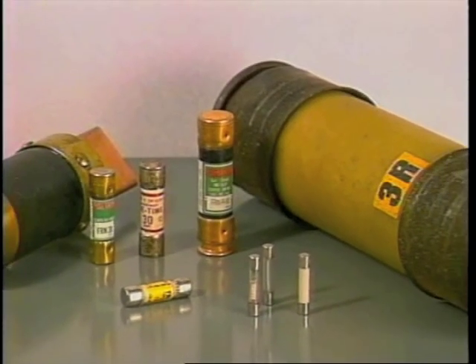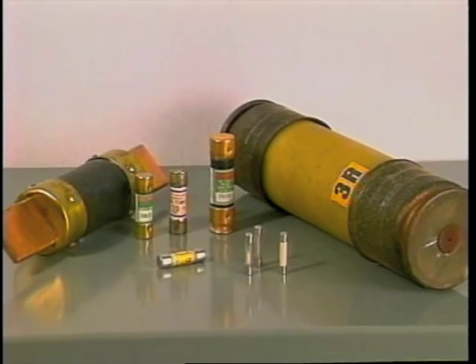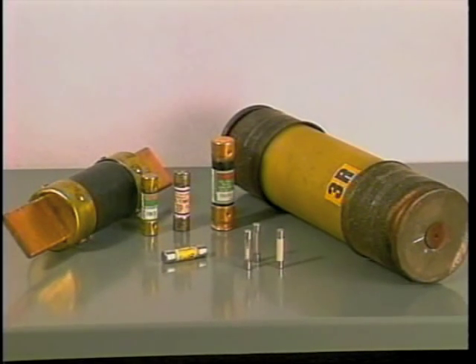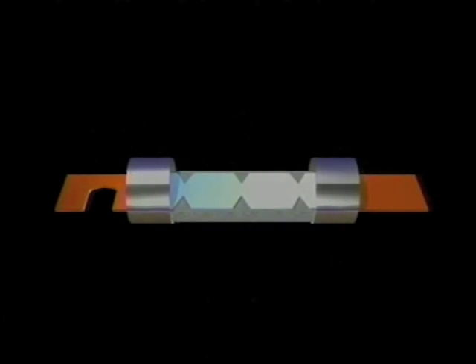One of the more reliable types of overcurrent protective devices is the fuse. The fundamental element of a fuse consists of a fusible link or links enclosed in a tube and connected to contact terminals. The electrical resistance of the link is very low and it acts as a conductor. When current in the circuit exceeds the fuse size, the link melts and opens the circuit to protect the conductors, other circuit components, and equipment.